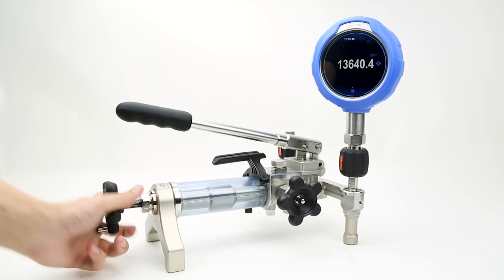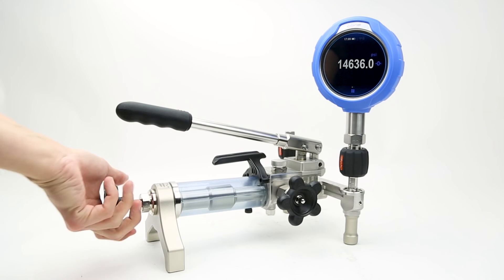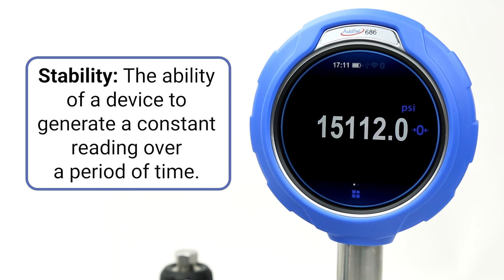When realizing a set point, a technician will often wait for the measured value to stabilize for a moment before taking a reading. The stability of a device is its ability to remain constant over time and will often be characterized as a percentage of the full range of the device.